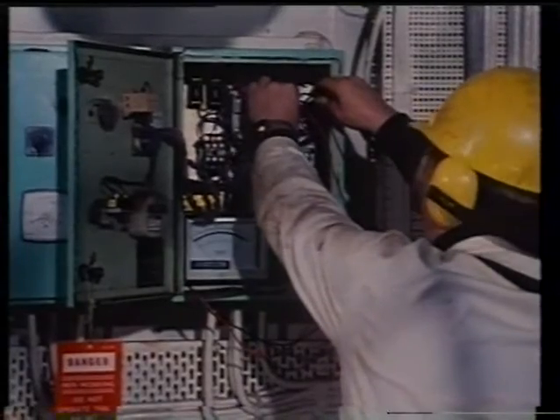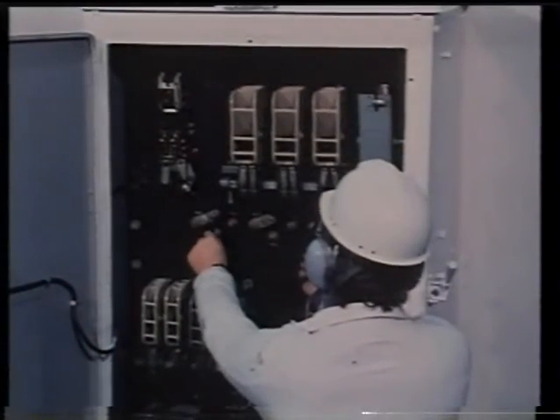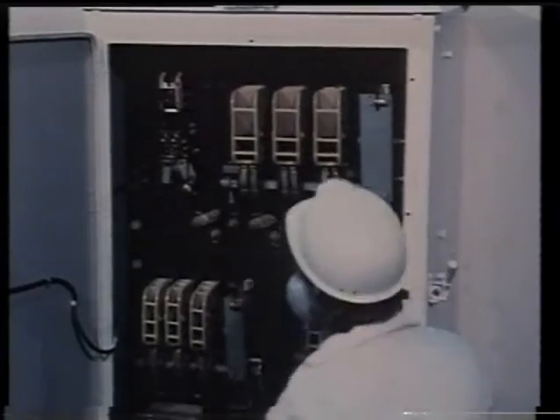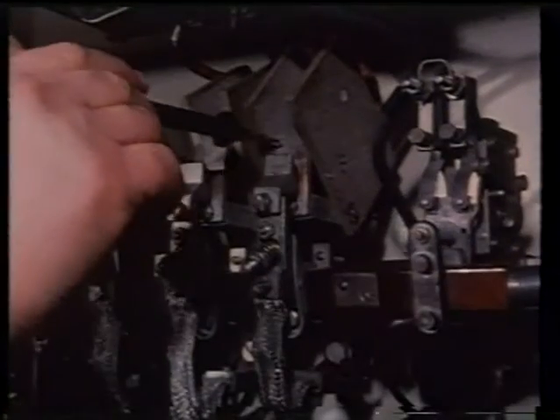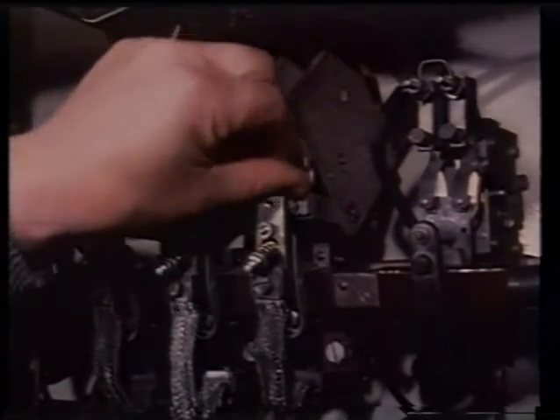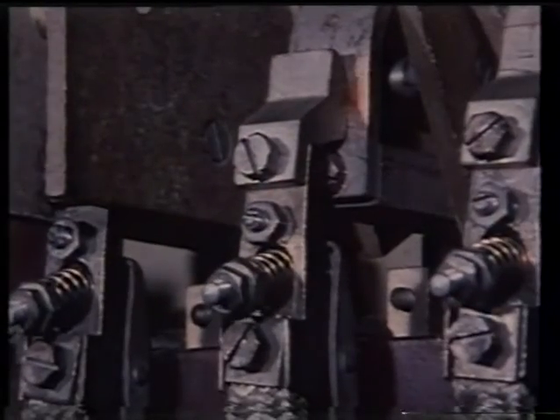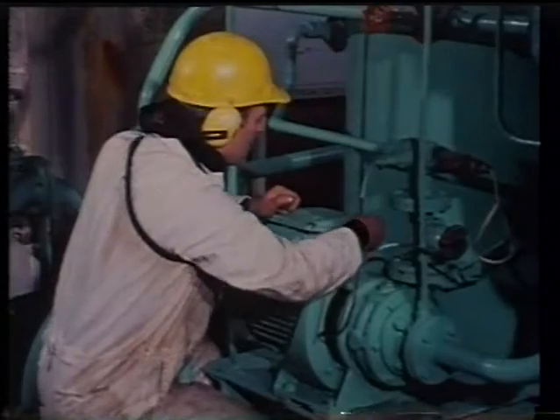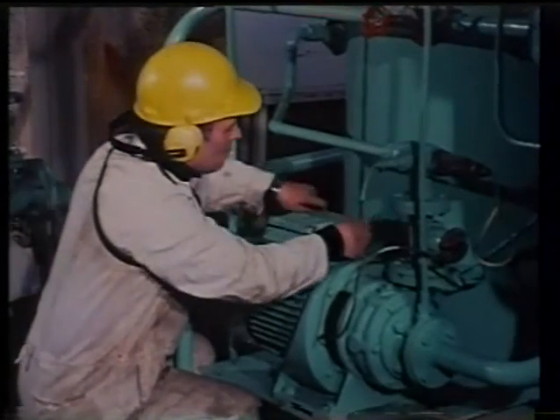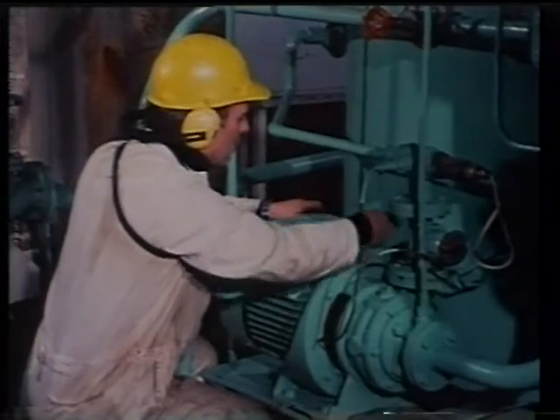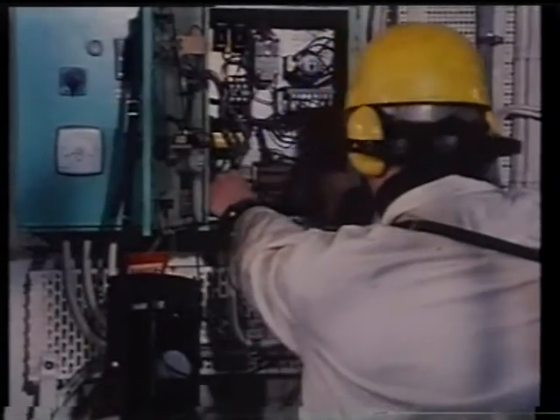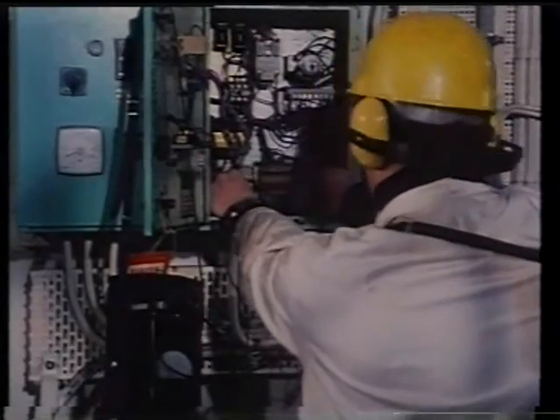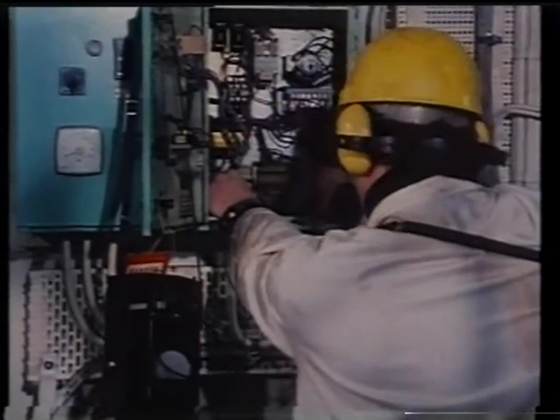Check and clean all starters, as the surveyor will probably conduct spot checks on starters. He will look for badly burned or misaligned contacts, loose connections, worn pigtails on moving contacts, and signs of overheating on coils, transformers and resistors. Check that all motor stator windings are clean and dry. The surveyor may take 1 or 2 ventilating grids off to inspect the windings for cleanliness and dryness. This applies particularly to drip-proof, weatherproof and deck watertight enclosures. The surveyor will want to look for the ingress of water or oil.